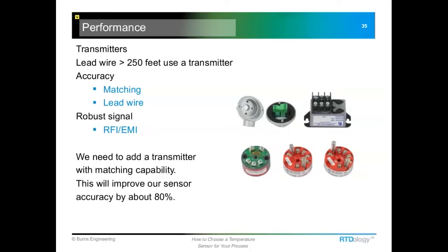So typically, as another rule of thumb, if you have more than 250 feet between the measurement point and a transmitter or your temperature controller or whatever it may be, it's a good idea to put a transmitter back at the temperature measurement point and just be sending that 4 to 20 milliamp signal or a voltage signal or whatever it might be, digital. It eliminates some potential errors with lead wires and electrical noise, those kinds of things. Radio frequency and electromagnetic interference can mess up an RTD resistance measurement that a signal conditioner may be doing.